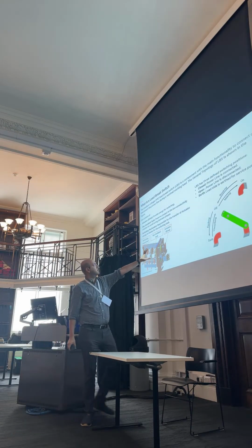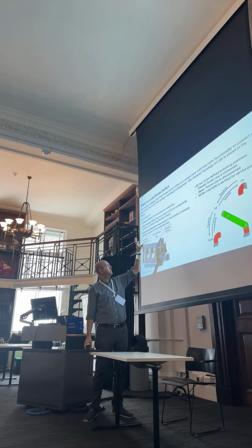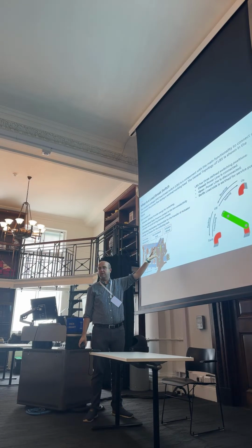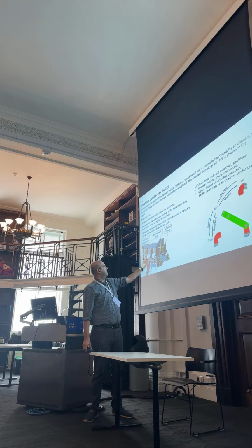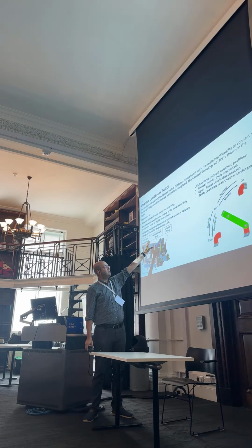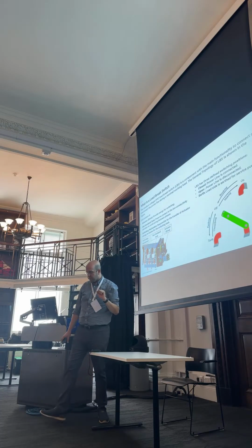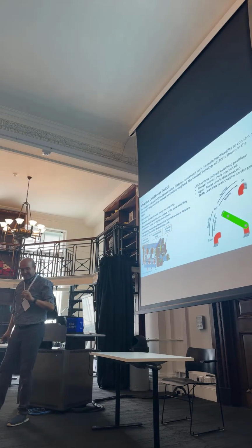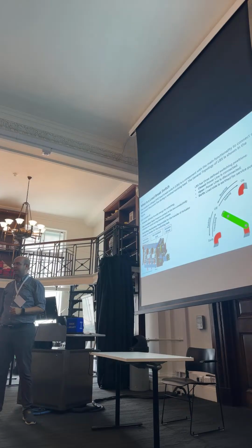And this drive consists of an actuator, which is a mechanical, electromagnetic device, providing the motion for the switchgear mechanics. So the switching mechanism, which is actually physically connecting and disconnecting the line, and the gas insulated tank. So the topic of SF6 is important for this gas insulated tank. This tank has many functionalities.